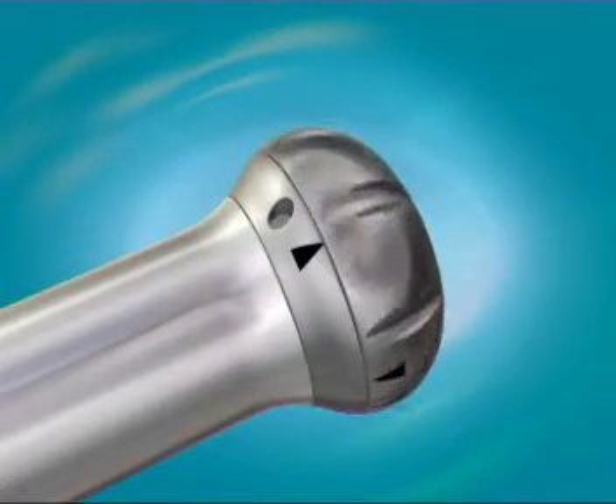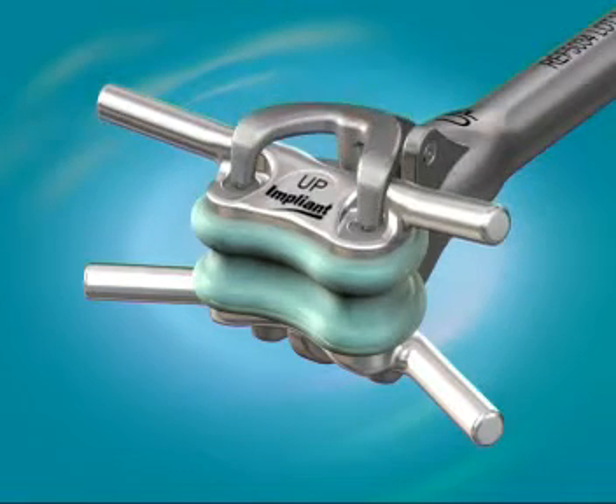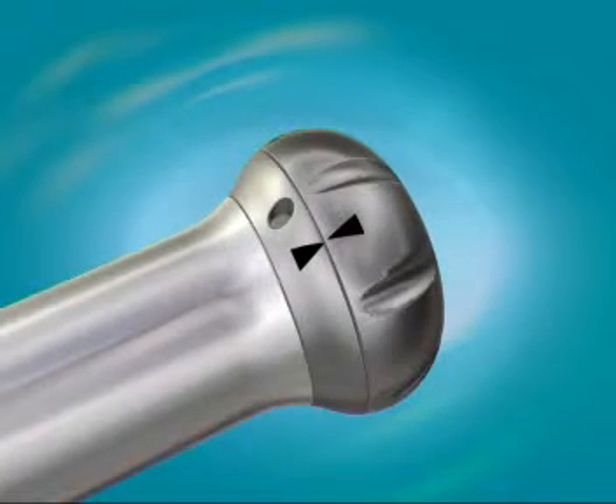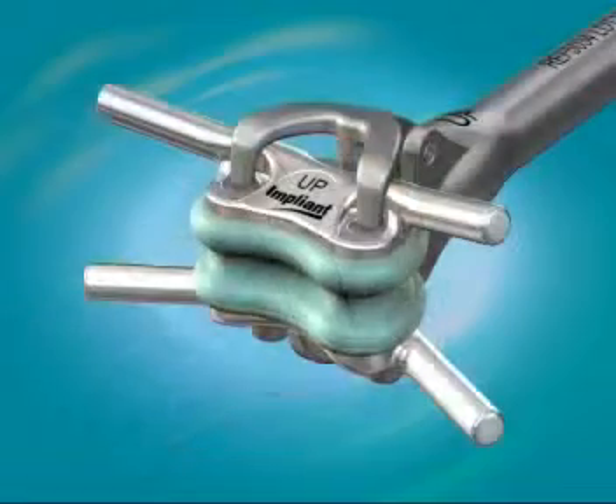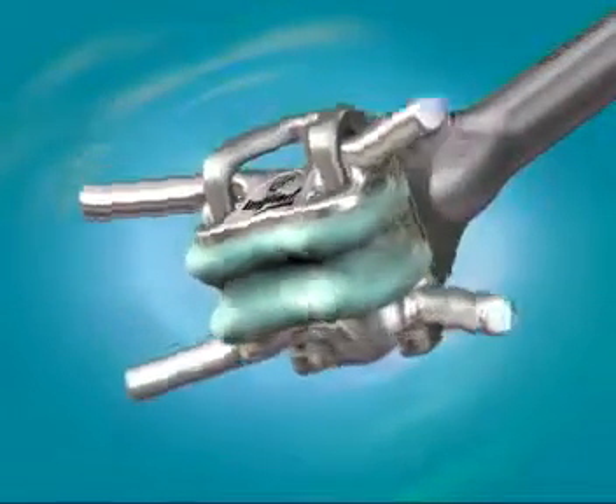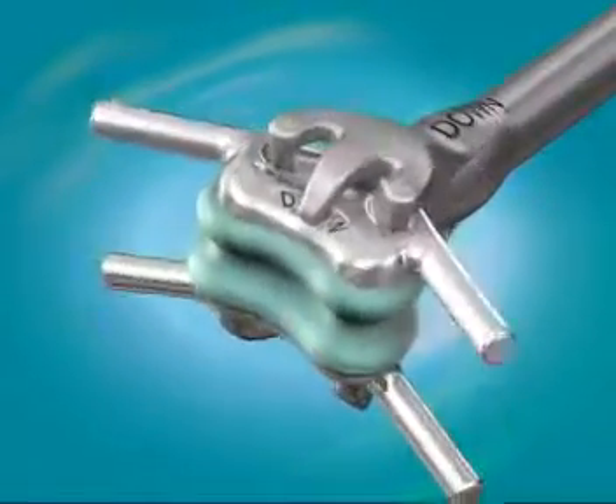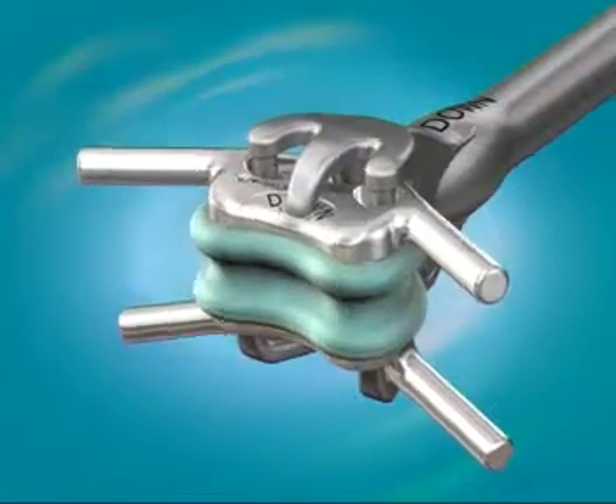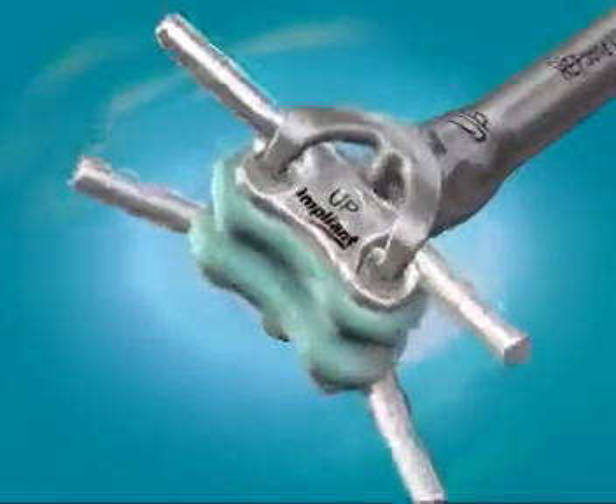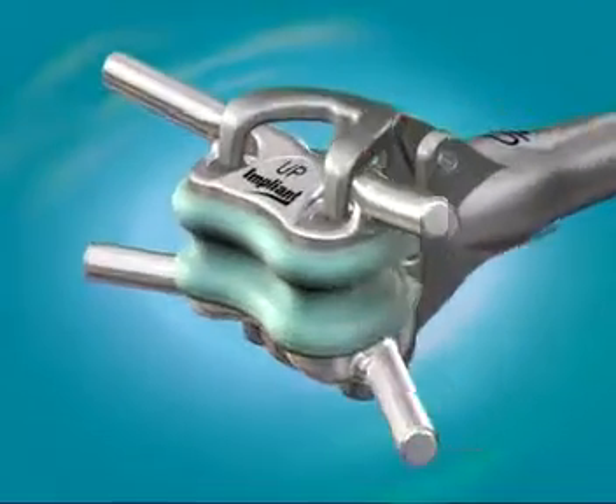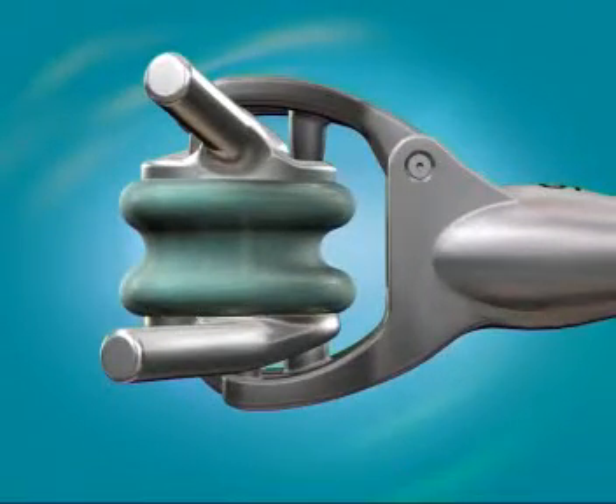With a clockwise motion, close the holder tongs. The 2 arrows will be aligned, verifying that you have successfully completed this step. As an added precaution, verify that the down marking on the holder matches the down marking on the TOPS device, and that the socket pins fit properly into the TOPS sockets.